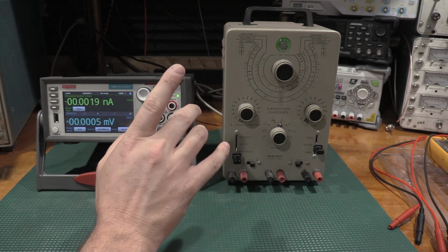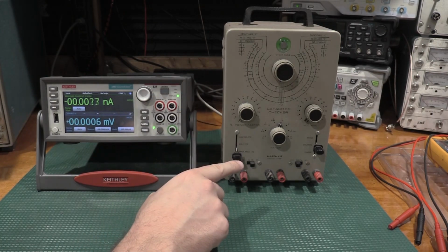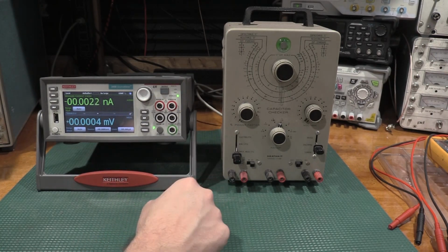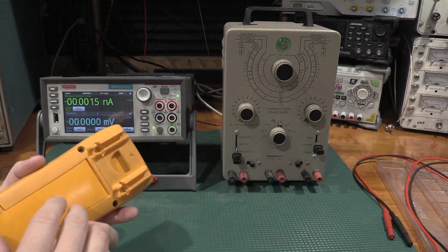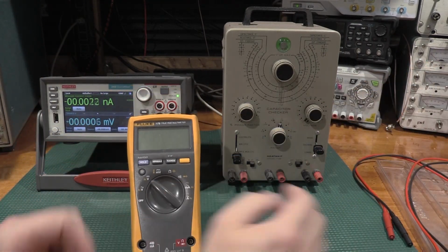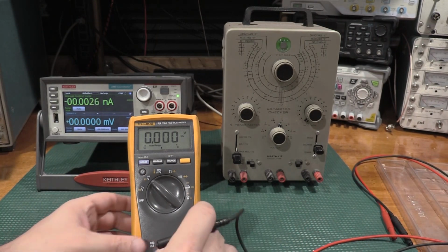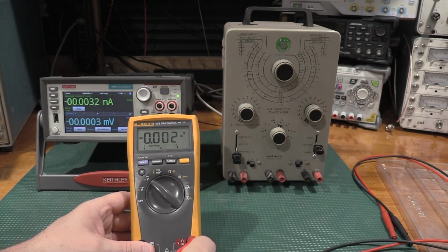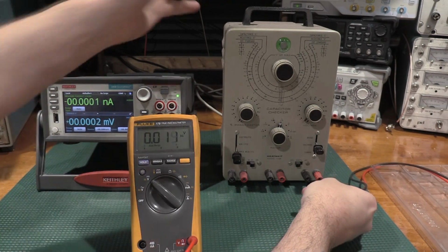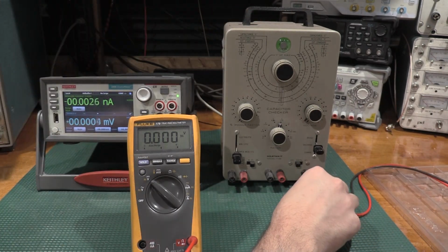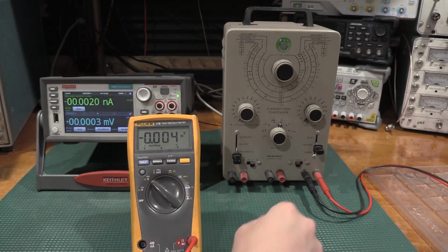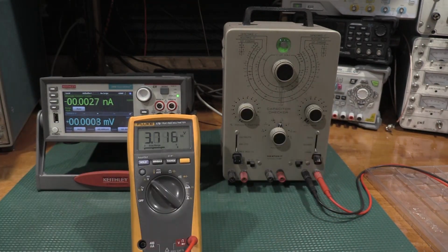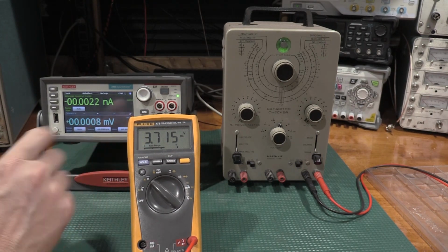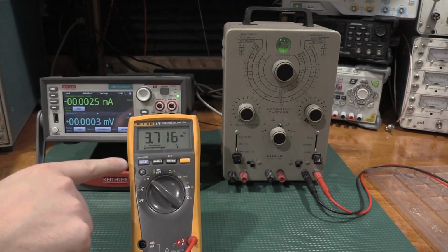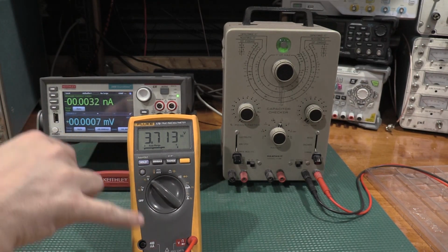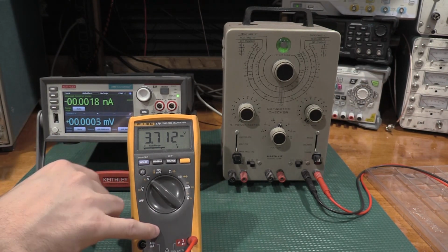So one of the problems with this thing is it has an unregulated power supply. Now, what we can do, we can prove that with the Fluke. And because it has an unregulated power supply and my line voltage running kind of hot, now these have been on for probably about half an hour, so they're nice and warmed up. We have it on the 3-volt setting. We'll hit leakage, and we're at 3.7. And you'll see the eye is closed because the meter impedance is too much current to open the eye.